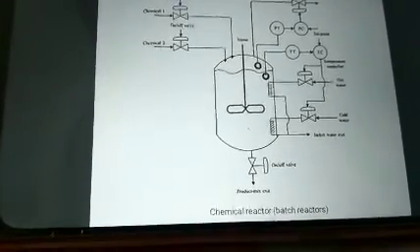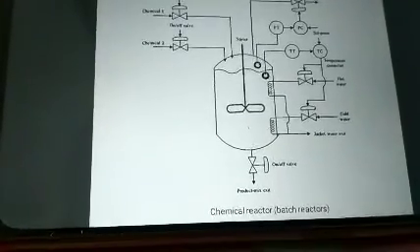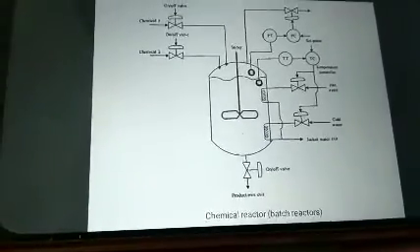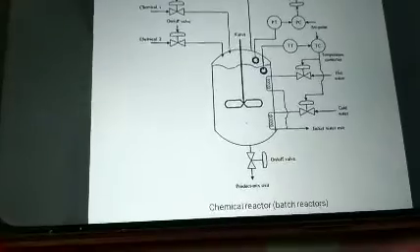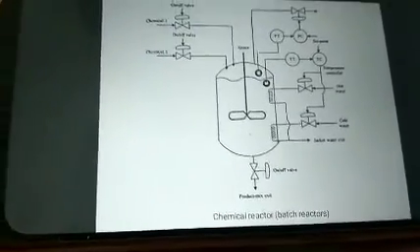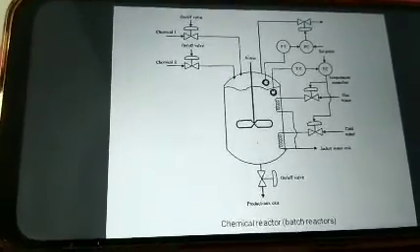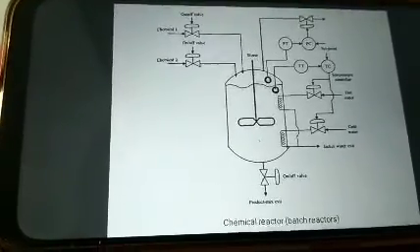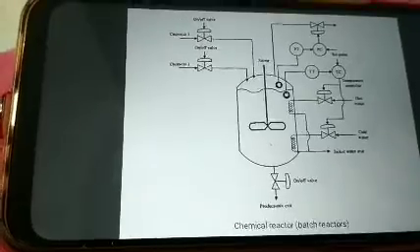The hot or cold water flow, the flow of the chemicals into the reactor, and the flow of the product mix out of the reactor are controlled by adjusting the respective valves. The pressure inside the reactor and the temperature of the product mix need to be continuously monitored. Now, for implementing the computer control, these actions or sequences are put up as logical steps in the form of a program when the entire sequence is designed.